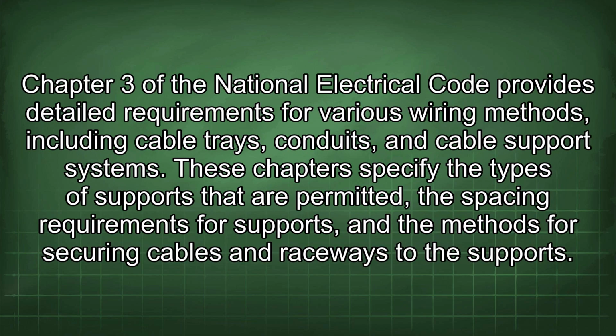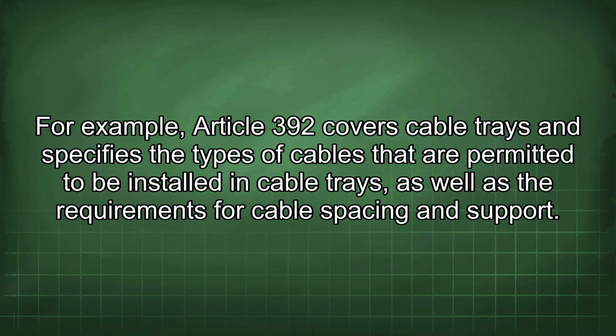Chapter 3 of the National Electrical Code provides detailed requirements for various wiring methods, including cable trays, conduits, and cable support systems. These chapters specify the types of supports that are permitted, the spacing requirements for supports, and the methods for securing cables and raceways to the supports. For example, Article 392 covers cable trays and specifies the types of cables that are permitted to be installed in cable trays, as well as the requirements for cable spacing and support.